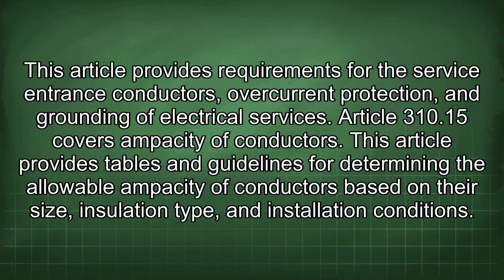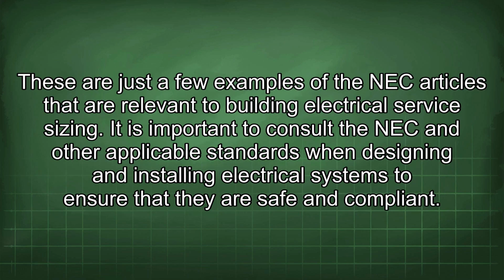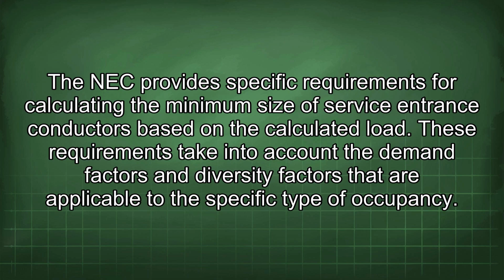Article 310.15 covers ampacity of conductors. This article provides tables and guidelines for determining the allowable ampacity of conductors based on the size, insulation type, and installation conditions. These are just a few examples of the NEC articles that are relevant to building electrical service sizing. It is important to consult the NEC and other applicable standards when designing and installing electrical systems to ensure that they are safe and compliant. The NEC provides specific requirements for calculating the minimum size of service entrance conductors based on the calculated load.